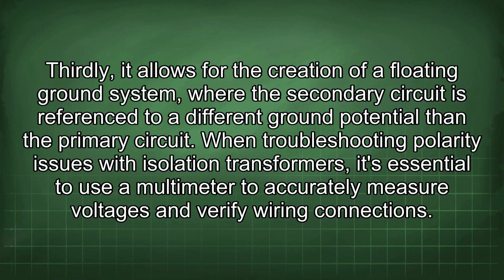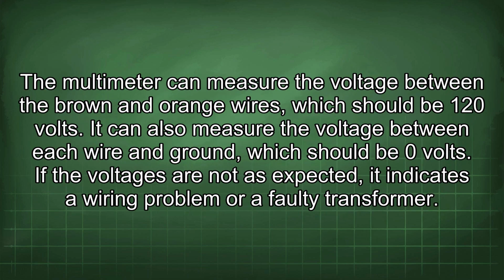When troubleshooting polarity issues with isolation transformers, it's essential to use a multimeter to accurately measure voltages and verify wiring connections. The multimeter can measure the voltage between the brown and orange wires, which should be 120 volts. It can also measure the voltage between each wire and ground, which should be 0 volts. If the voltages are not as expected, it indicates a wiring problem or a faulty transformer.